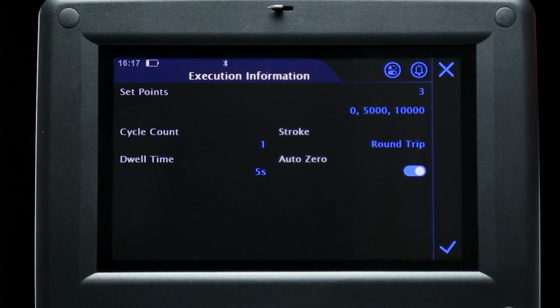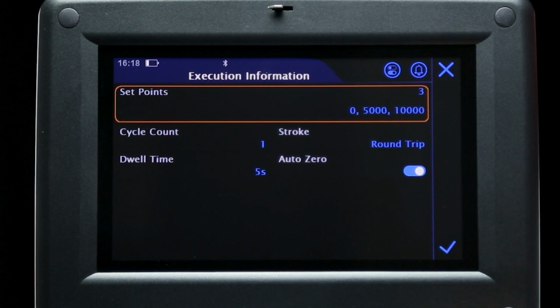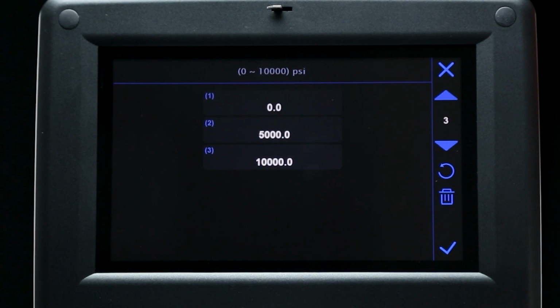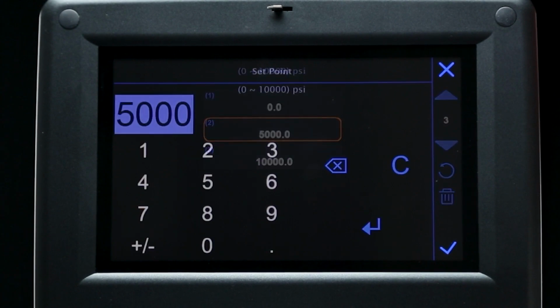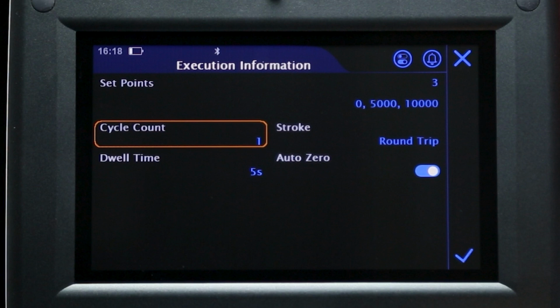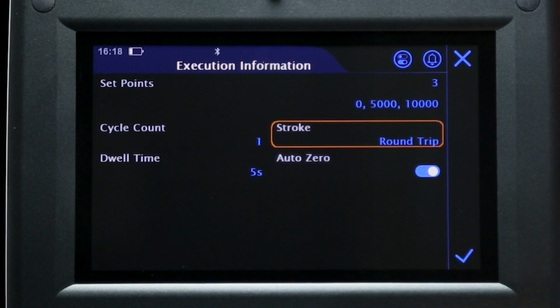The 762 will now ask for specifics of the test procedure. Changing the set points will automatically distribute the pressure values according to the previously set range, but you can also set custom values by selecting any of the set points on the screen. Cycle count will determine how many times the test should be performed, while stroke allows the user to select a round trip or one-way pressure test.